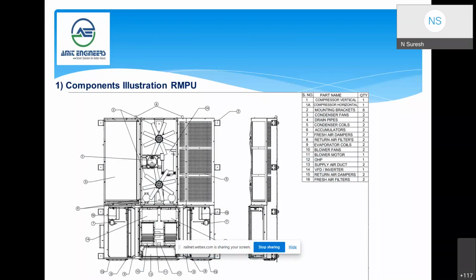I think during this slide only it was not clear. So this is the overall components illustration: one vertical compressor, one horizontal compressor, 8 mounting brackets, 2 condenser fans, drain pipes, 2 condenser coils, 2 accumulators, 2 fresh air dampers, 2 return air filters, 2 evaporator coils, 2 blower fans, and one double shaft blower motor, heater overheat protections, supply air duct, VFD, variable frequency drive, and return air dampers and fresh air filters.